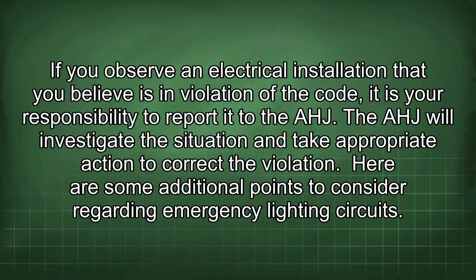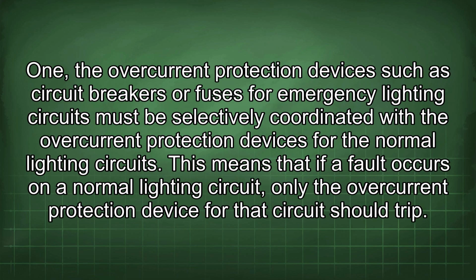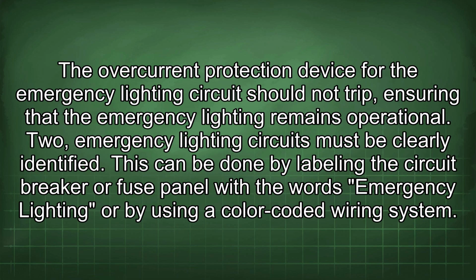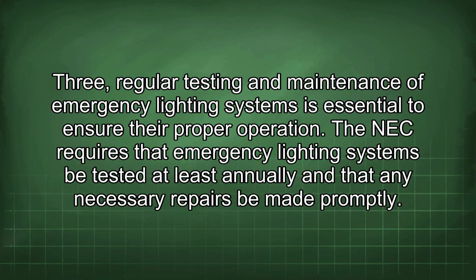Here are some additional points to consider regarding emergency lighting circuits. 1. The overcurrent protection devices such as circuit breakers or fuses for emergency lighting circuits must be selectively coordinated with the overcurrent protection devices for the normal lighting circuits. This means that if a fault occurs on a normal lighting circuit, only the overcurrent protection device for that circuit should trip. The overcurrent protection device for the emergency lighting circuit should not trip, ensuring that the emergency lighting remains operational. 2. Emergency lighting circuits must be clearly identified. This can be done by labeling the circuit breaker or fuse panel with the words emergency lighting or by using a color-coded wiring system. 3. Regular testing and maintenance of emergency lighting systems is essential to ensure their proper operation. The NEC requires that emergency lighting systems be tested at least annually and that any necessary repairs be made promptly.